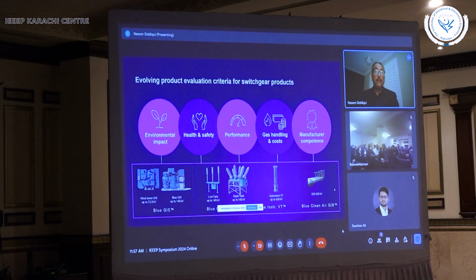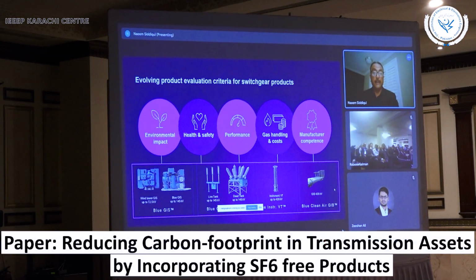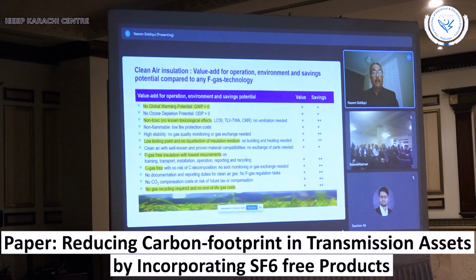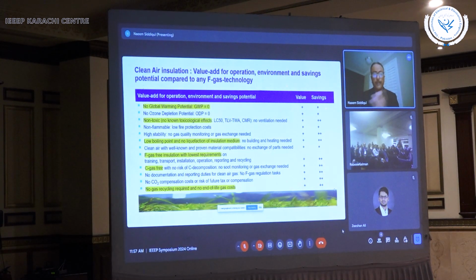So evolving basically product evaluation criteria for switchgear product is, you can see basically has been changed in the last 5 years in different basically regions. And environmental impact is the number one, health and safety, performance, gas handling, and manufacturer competence. These are the criteria based on that different switchgear equipment customers and utilities they are selecting. So if you look at clean air from advantages point of view, this is the most basically known gas. We are breathing in it every day, every minute, every second. I don't want to basically again read each and everything line by line, but has a lot of basically advantages if you are using clean air instead of SF6.